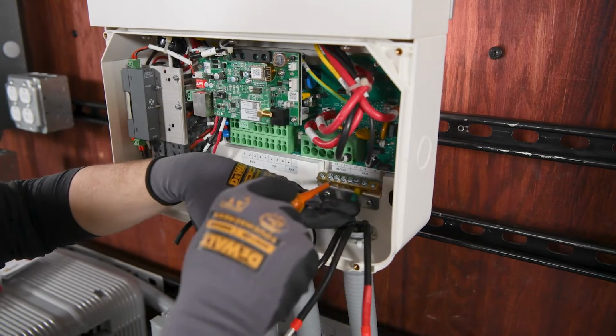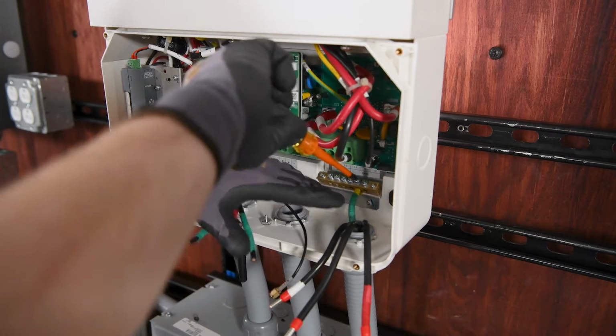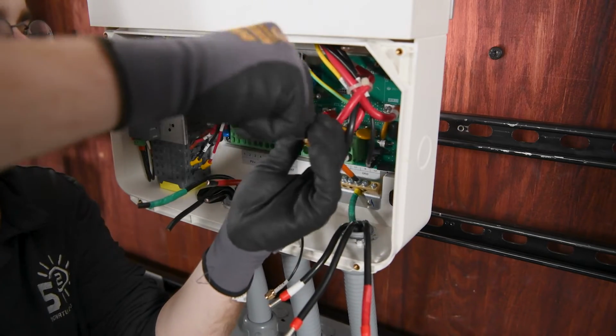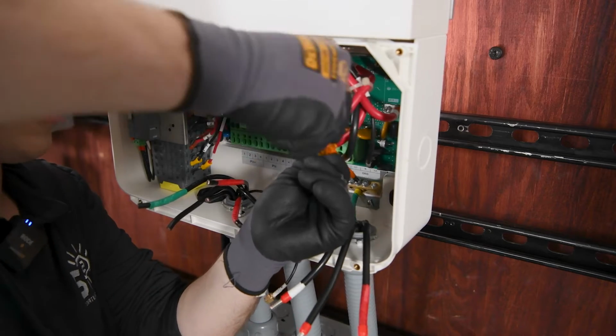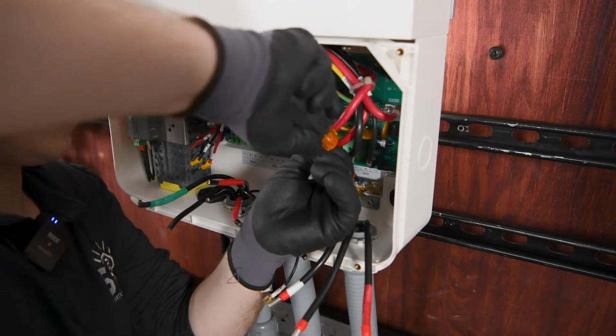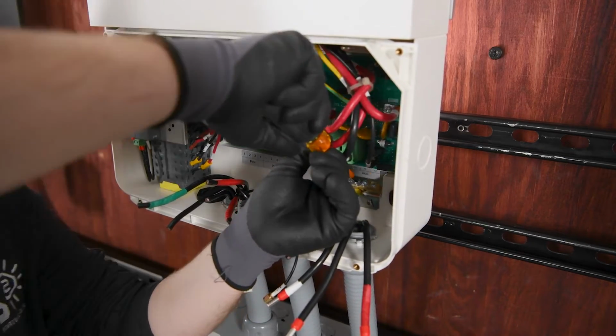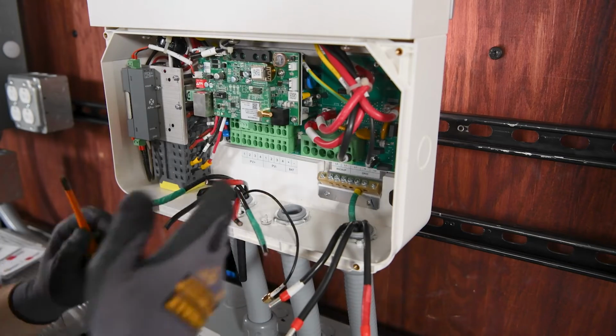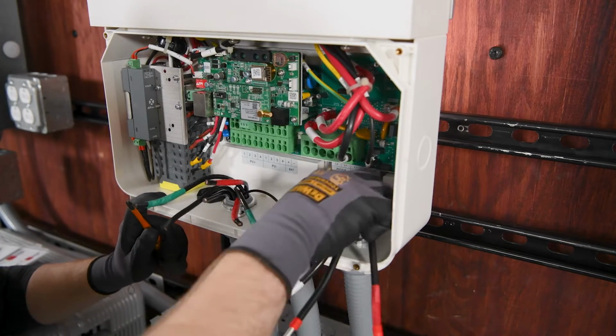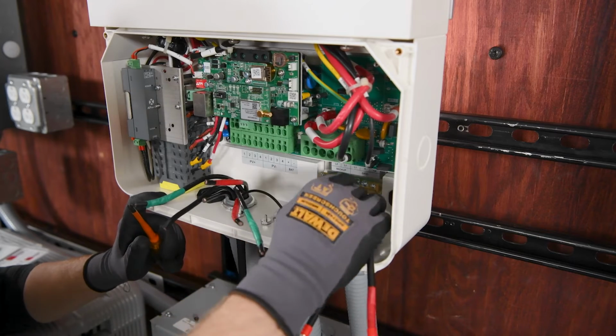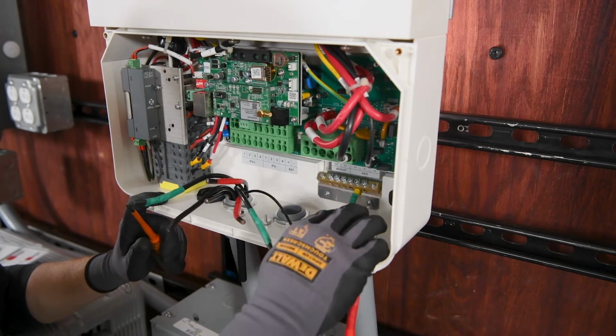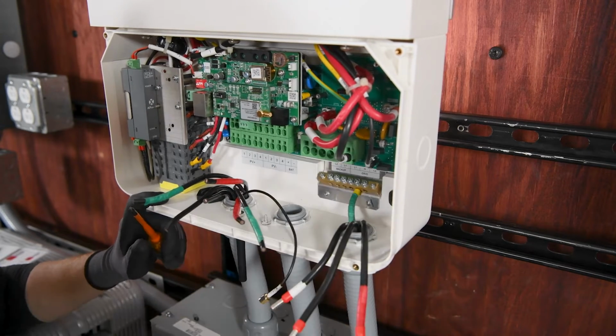So for our grounding terminal block here, we're just going to use a Phillips head screwdriver and ensure that it is fastened tightly. Now, it's always recommended to torque these to specs, and also to do a pull test is what I like to do to make sure that it has a nice secure contact with whatever it's connected to. So ground's not going anywhere.